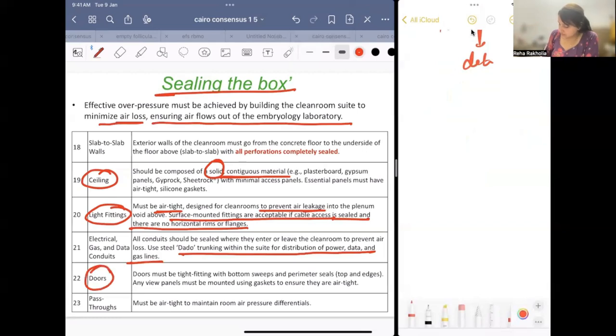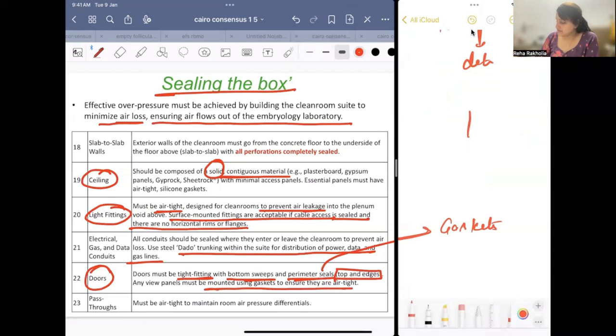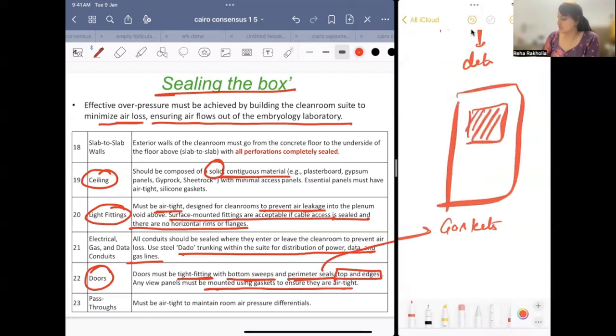Doors must be tight fitting with bottom sweeps and a perimetric seal at top and edges, achieved with gaskets. Any view panel must be mounted using gaskets. This glass view panel should be gasketed and sealed. Pass-throughs must be airtight to maintain room air pressure differentials.